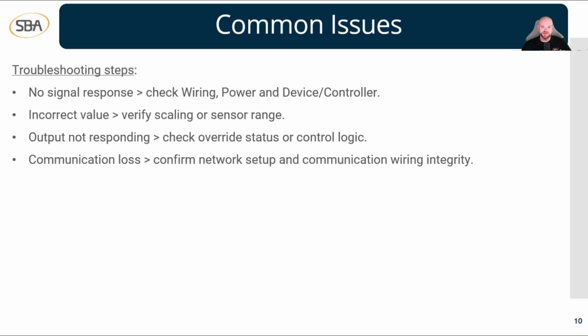So if we've checked to make sure already, if we've done the point-to-point checkout on this specific output, and we have found that it does work with just overriding the point, and then we release everything and let the logic run the point itself, but it's not commanding anything, then I would say we probably have something in our logic that's keeping the output from being commanded on. So again, if your output's not responding here, just check the override status and check your logic on this. Probably the most common errors for those.